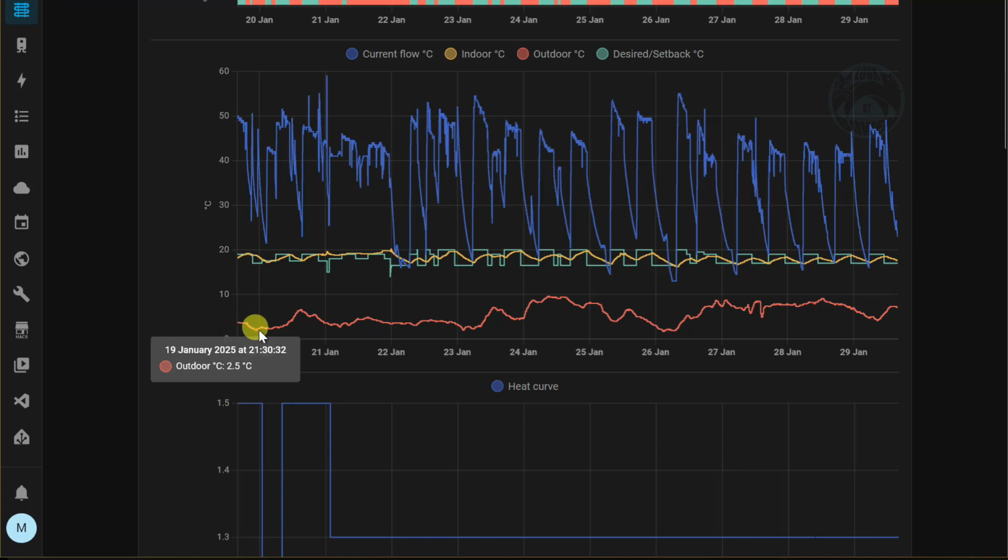And when the temperature is dipping down to close to zero, and all you are trying to achieve is warming your house, if you're not warming your house, you're going to make a lot of changes. And changes on a regular basis is not a good thing for this type of boiler because any change takes a couple of hours or even a couple of days to reflect correctly, which is why I had to revert to using Home Assistant to monitor what was going on in the boiler.